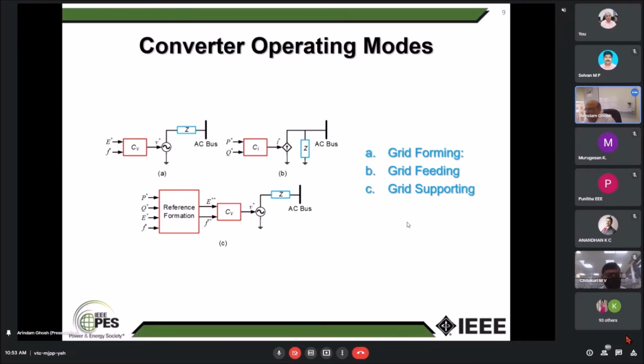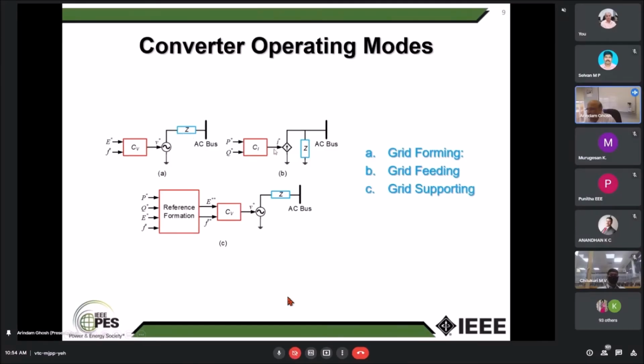Whereas in grid feeding, you are given a P and Q reference, real and reactive power reference, and from these two references you generate a current and inject it into the AC bus. For example, in maximum power point tracking in a PV, the MPPT uses a DC-DC converter that sets the P reference, and suppose your Q reference is 0, then you convert it into a current source and inject it with the grid at the same frequency as the grid. Paralleling these is much easier than paralleling voltage sources, because voltage sources have the problem of holding one voltage.